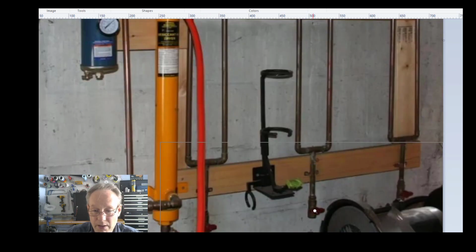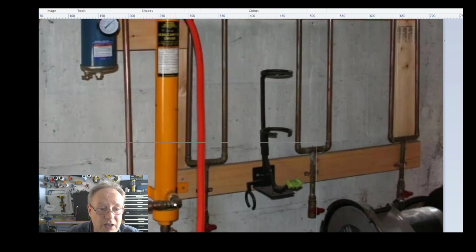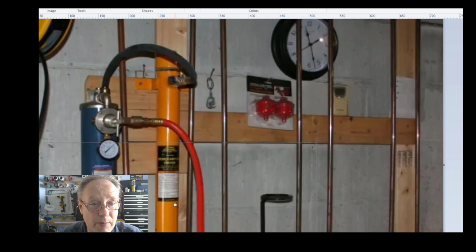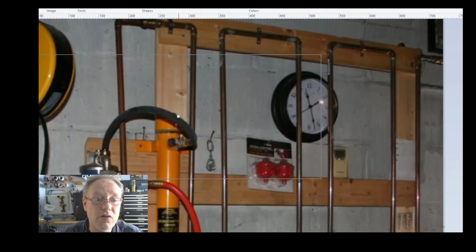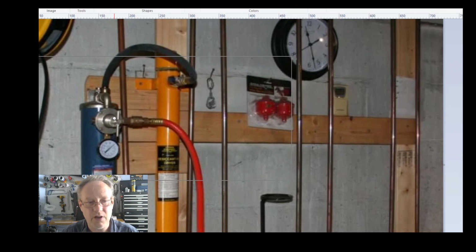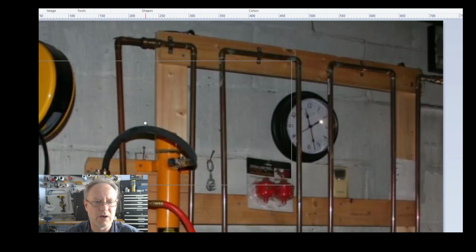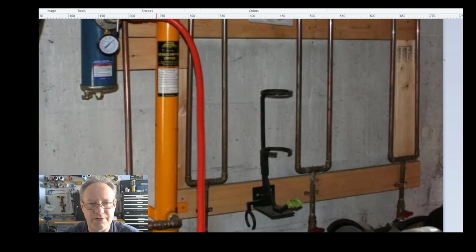At some point, somebody's going to undo these valves to get all this water out. Then this air comes all the way down here, and it goes into the moisture separator, does the same thing, comes out of the moisture separator, and then goes into some kind of filter and a pressure regulator. So this pressure regulator is after the water separation. And then that's your line. That red line goes to whatever system is using this air.